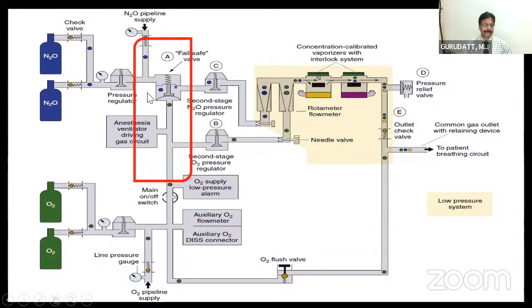They are present mainly just downstream of the primary pressure regulators and upstream of second stage pressure regulators in GE machines and upstream of flow meter assembly in the Draeger machines, because in the Draeger machines we don't have the second stage pressure regulators. So these fail-safe valves are again depending on the workstation, whether we have a GE machine or whether we have a Draeger machine, they're slightly different. So let me just discuss about these fail-safe valves of GE and Draeger machines.